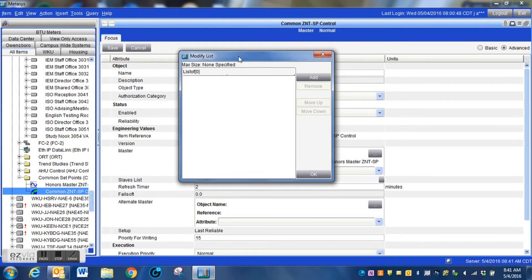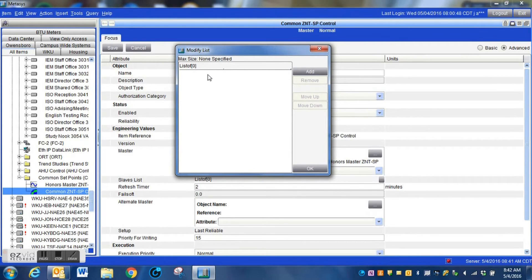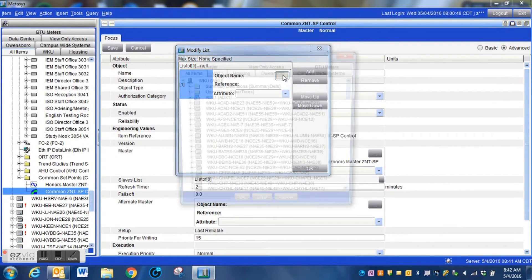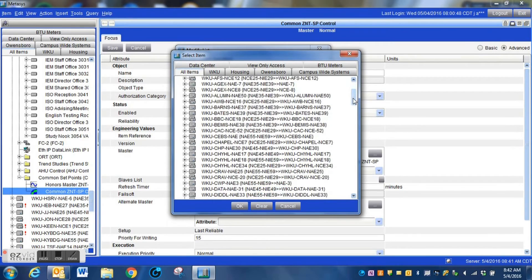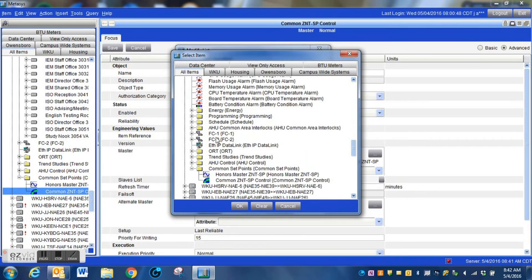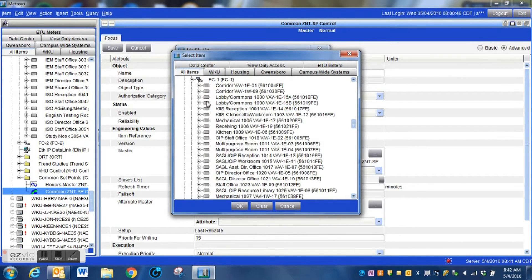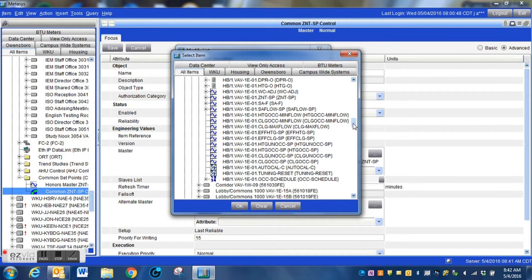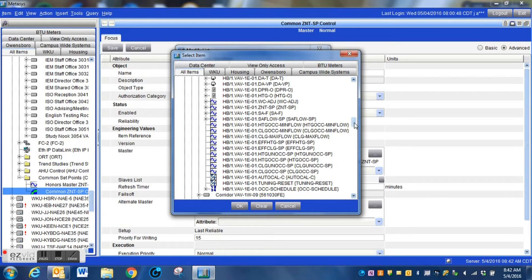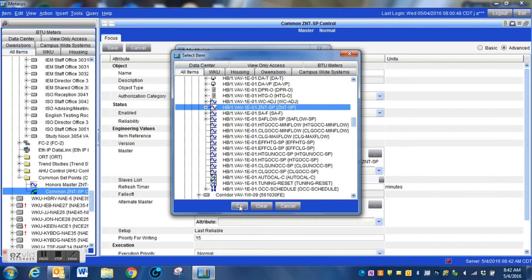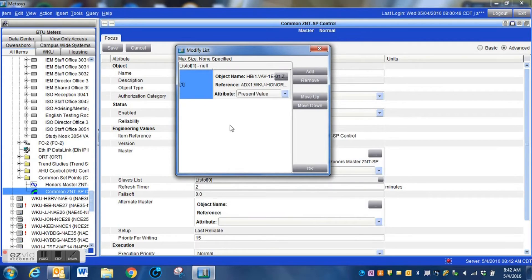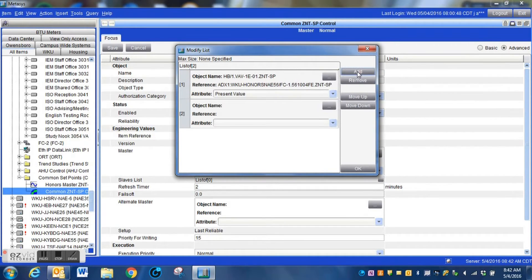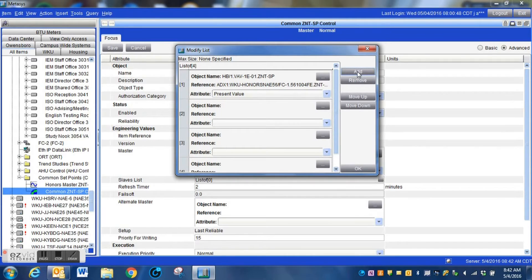You press this little gray box, it's going to pop up this little window here. Each point has to be added individually. Once you add one of these boxes here, you press add, it creates this little box. You'll see the gray box there, you will click it, and then you will go down to one of your VAVs. Start from the top or bottom, or however it's easiest for you. Simply drop down the VAV and find the individual point. In this case, we're going to grab the common zone set point of that particular VAV. We simply highlight that, and we press our OK button, and it has now linked that global data point to this particular VAV.